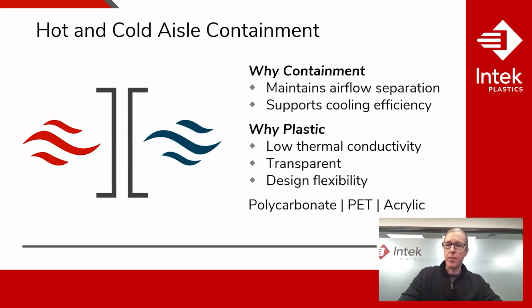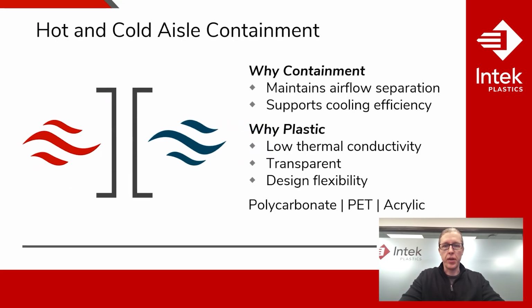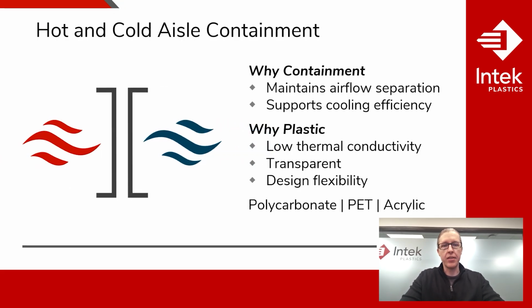Hot and cold aisle containment. With advancements such as direct-to-chip and immersion cooling, maintaining effective separation between hot and cold air streams remains a critical part of data center design. Temperature differentials between these zones can reach up to 60 degrees Fahrenheit, making material selection especially important.